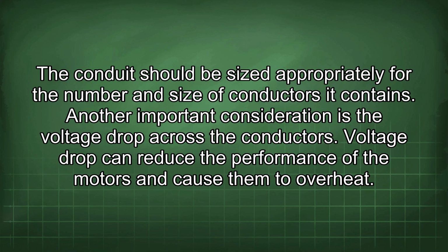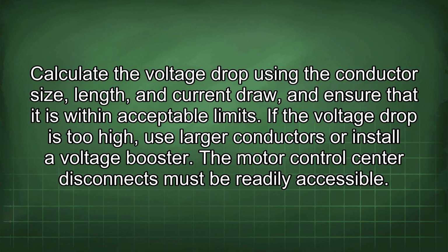Another important consideration is the voltage drop across the conductors. Voltage drop can reduce the performance of the motors and cause them to overheat. Calculate the voltage drop using the conductor size, length, and current draw, and ensure that it is within acceptable limits. If the voltage drop is too high, use larger conductors or install a voltage booster.